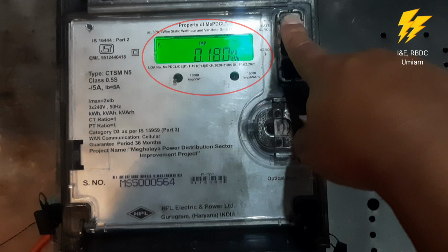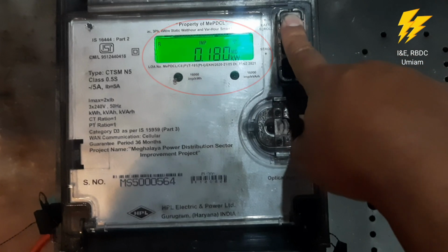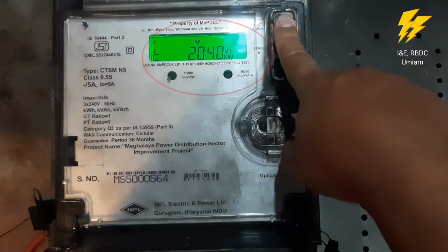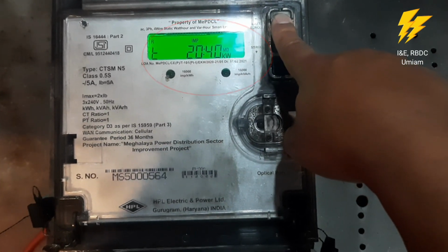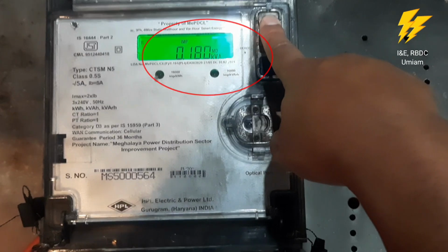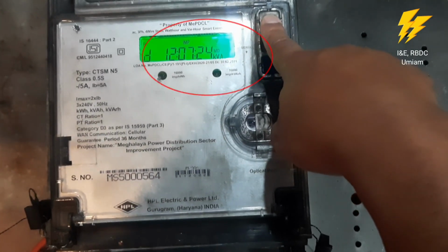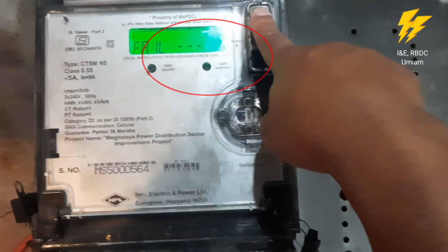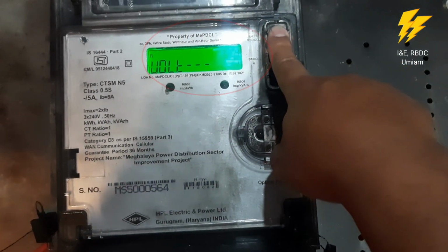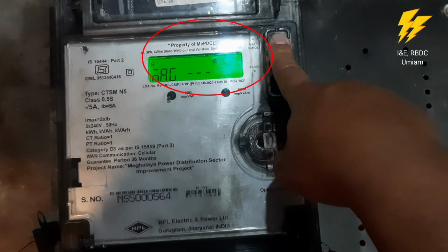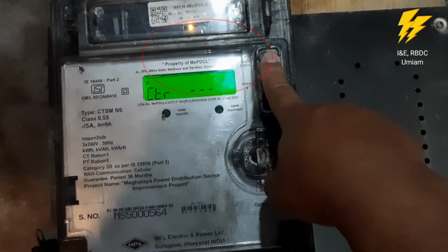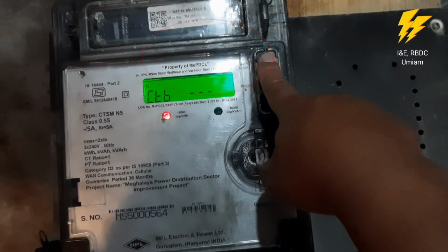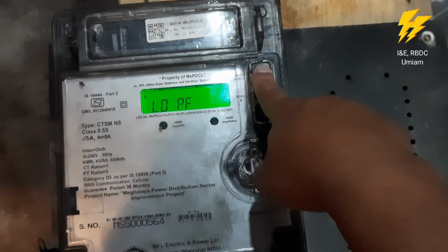All right, so like this, and then same thing, at what time this maximum demand took place, or on what date: on 12th of July, which is today's date, and at what time. All right, at 2040. And in terms of kVA also it will come the same, because kW is equal to kVA. Why? Because in this particular case my load is purely resistive, and because of that power factor is almost unity. And that is basic electrical engineering only, kVA will be equal to kW. So it happened today, the 12th, at 2040.